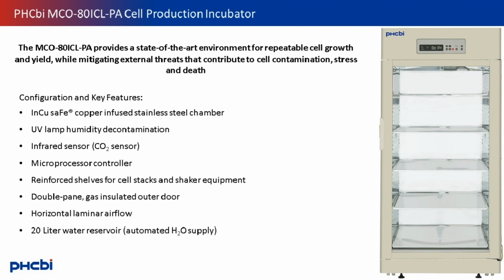Monitor and control parameters with a user-friendly microprocessor controller. If you are planning on using a heavier apparatus or apparatuses in your incubation, reinforced shelving can support your configuration. And a double-pane gas-insulated door guards against temperature, humidity, and CO2 fluctuations while maintaining a clear view of your cells. The cell production incubator was designed with side-perforated walls and horizontal laminar airflow to ensure a stable, uniform environment throughout the chamber and a quick recovery after door openings. An optional external 20-liter water supply was designed with the added humidity needs in mind.